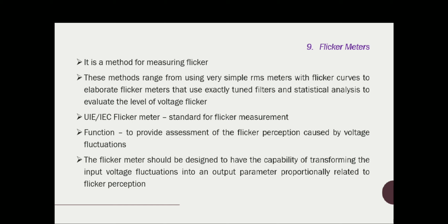Although the United States does not currently have a standard for flicker measurements, there are IEEE standards that address flicker. IEEE standards 141 1993 and 519 1992 both contain flicker curves that have been used as a guide for utilities to evaluate the severity of flicker within their system. In other countries, a standard methodology for measuring flicker has been established.